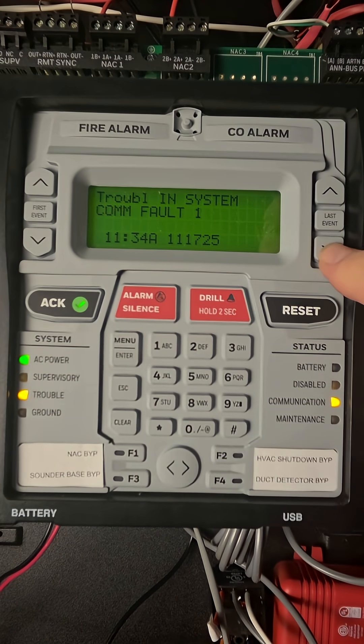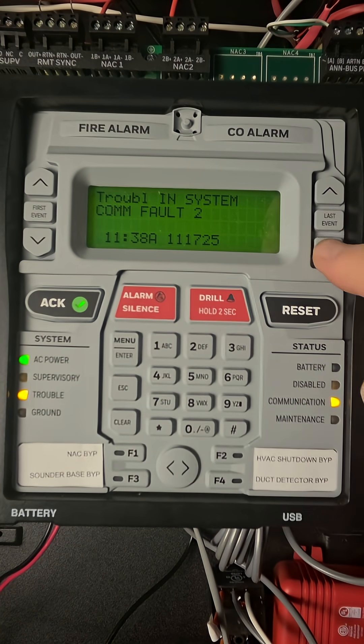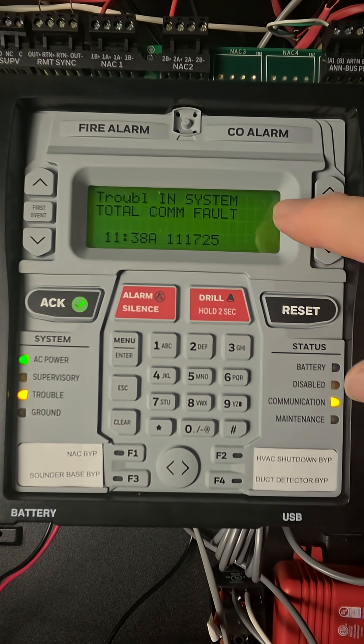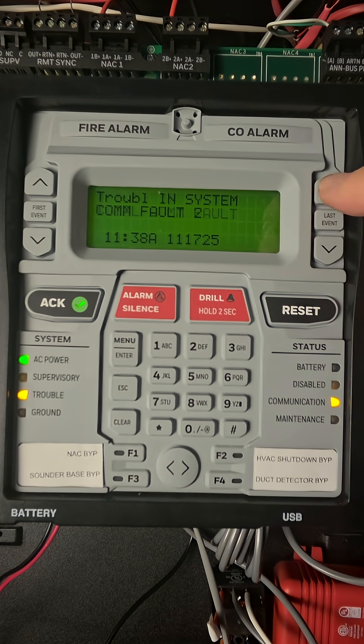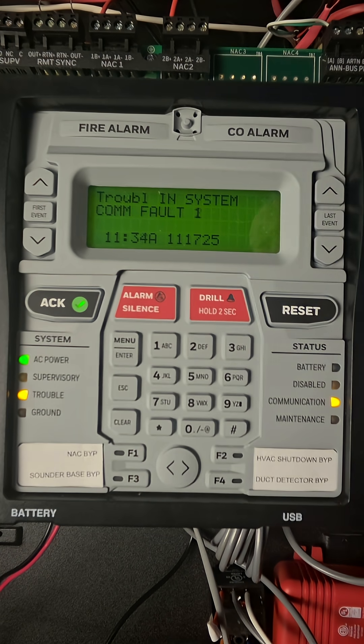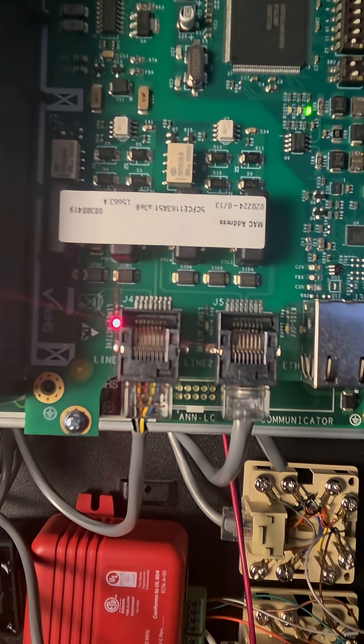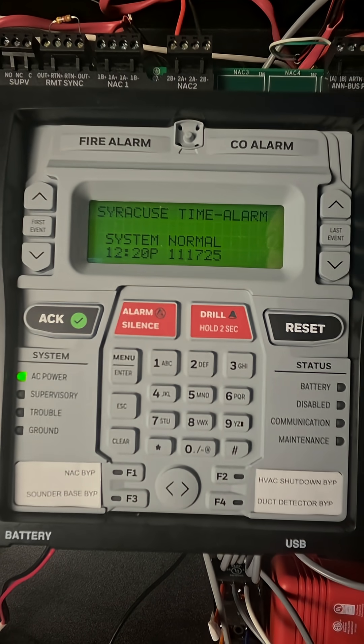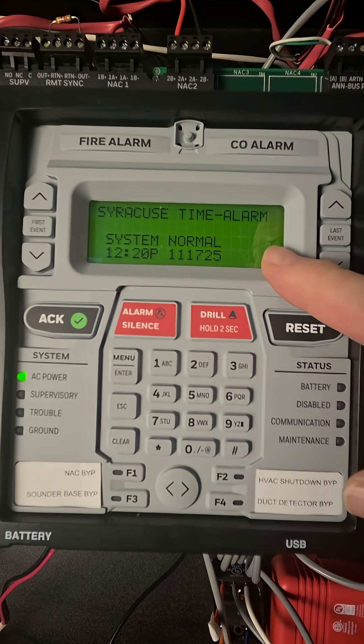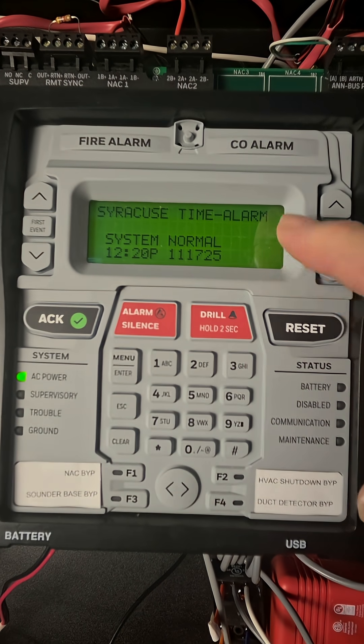Once cell service is re-established, we now have voltage on both of our phone line circuits. The system is going to remain in trouble until the onboard communicator can re-establish a connection with the monitoring service. Now it's attempting to connect, and when communication is established the system should go back to normal without having to reset.